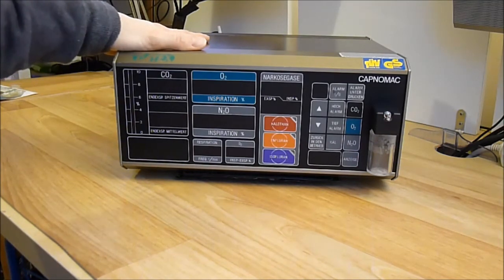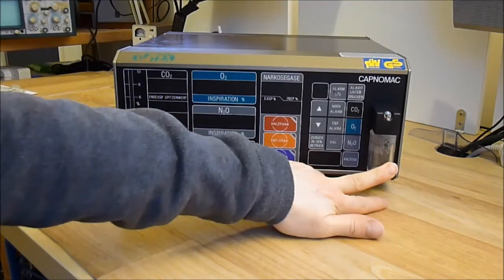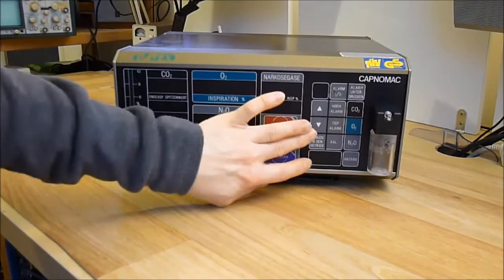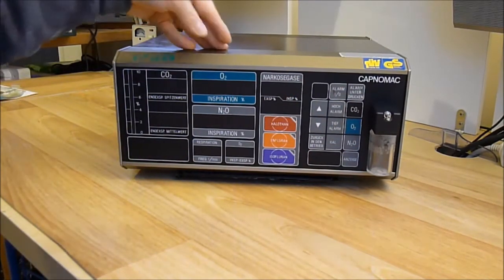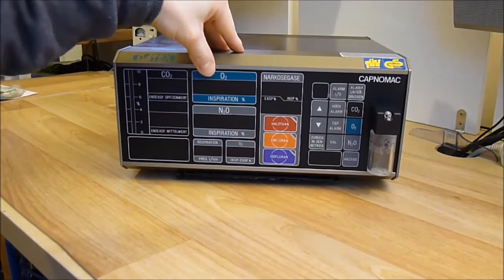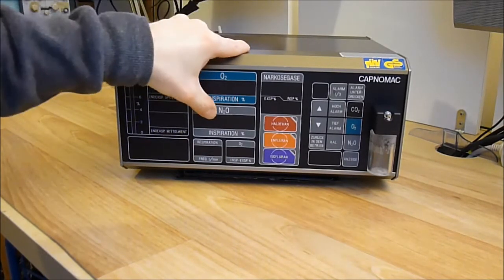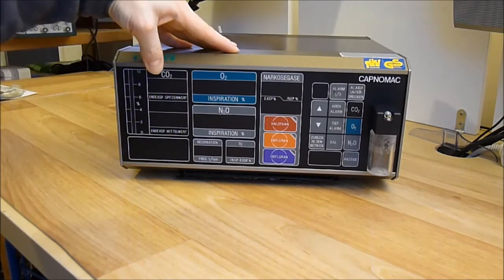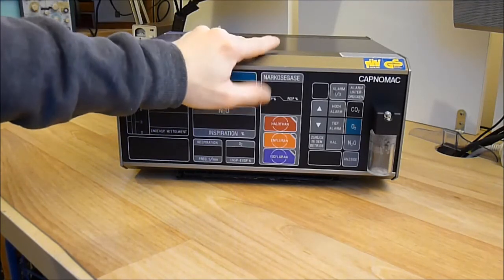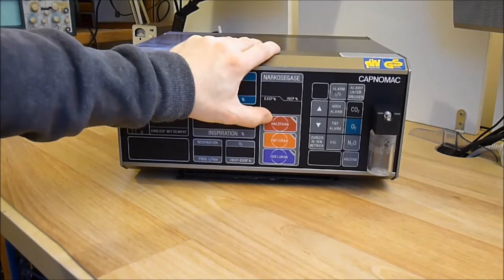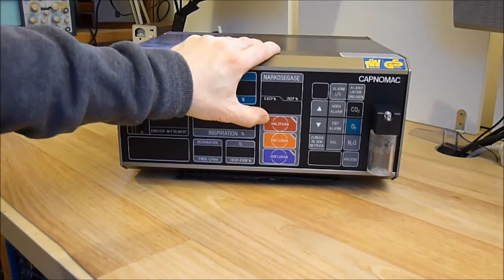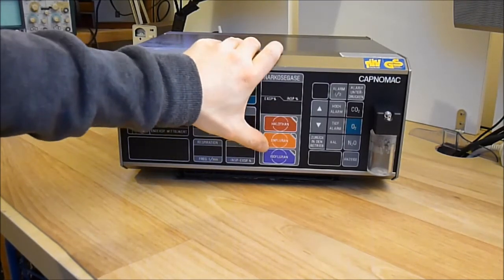So we have one air input here with a water trap. Quite a neat LED display and some keys. As you can see, it measures O2, N2O, CO2 and the anesthesia gas mixture. It works with three anesthesia gases: halothane, enflurane and isoflurane.